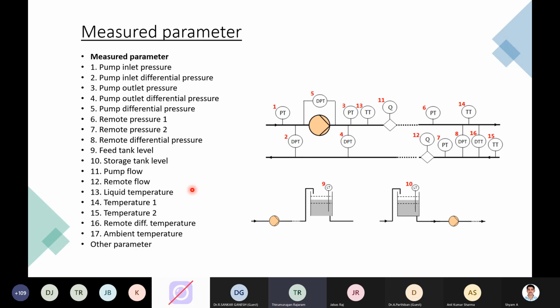So based upon your application, you can design whether the pump is operated on a PT, a DPT, a flow meter, or a temperature transmitter. Even for tank filling, what would be your optimized way? You can have a level transmitter, and start and stop based upon the level. Or if you are draining from your overhead tank into your system, you can also use a level transmitter. Such understanding of how you can automate makes a system more efficient, we can say.